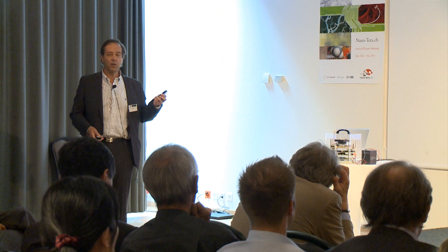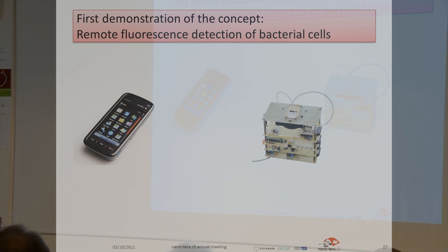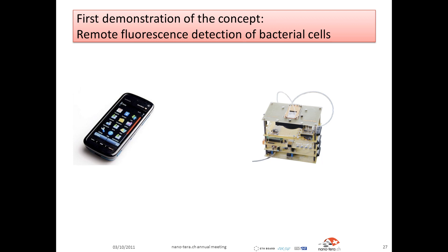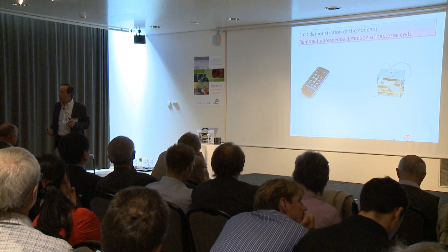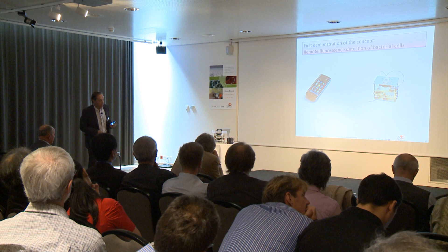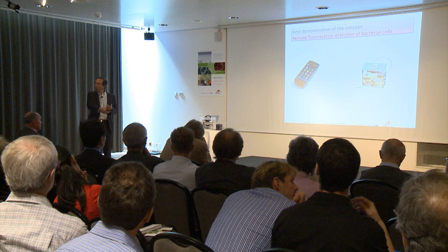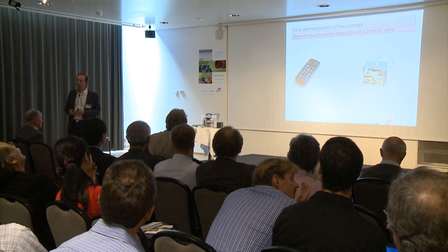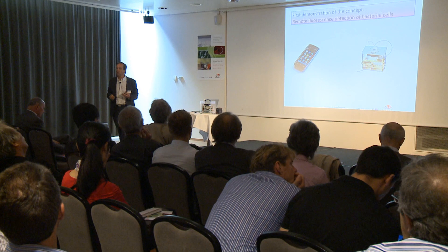And what I have in my hand is a Nokia phone — not an iPhone for once. As it is now with the demonstrator, I can call the system. There is no sound unfortunately, but I'm calling the system now. After three calls, the system turns on and starts the measurements. When the measurement starts, there is a pump — there's maybe some light blinking there. After a certain time of incubation, it reads the fluorescence of the bacterial sample, and it will send me back — in maybe 10 to 20 minutes — an SMS with the fluorescence level. This is the first demonstration. Next year I will come with a much more sophisticated demonstrator.